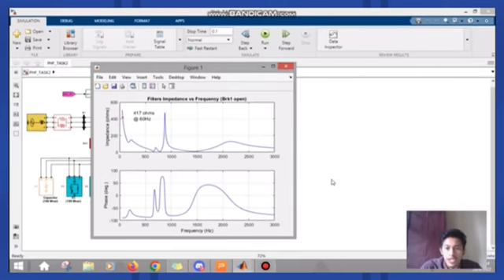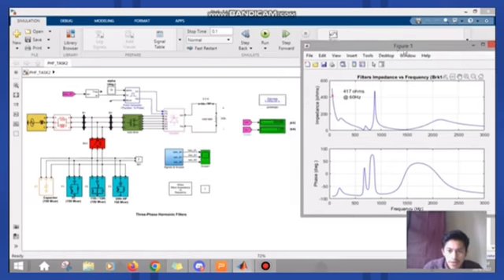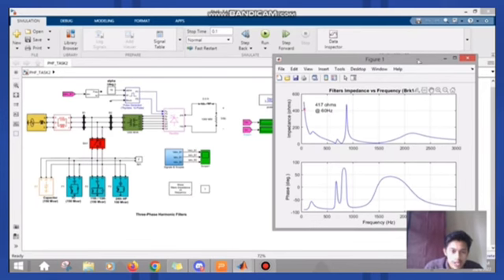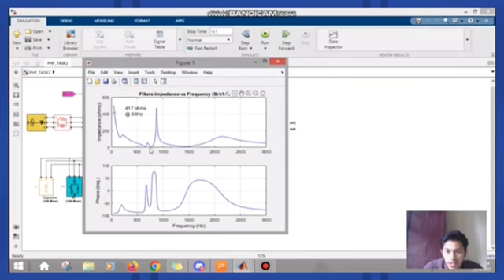The last part in this simulation is the impedance versus frequency graph. This shows the impedance versus frequency graph obtained from the impedance versus frequency block here. From the graph here, the plotted X shows the value of impedance, which is 417 ohm at frequency 60 Hz. From this value, the reactive power can be obtained by using the formula V squared over the value of impedance, which is 417. So the calculated value at the end is approximately 600 megavar. That's all from me. Thank you.